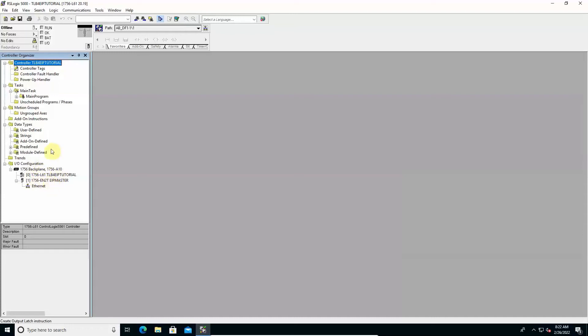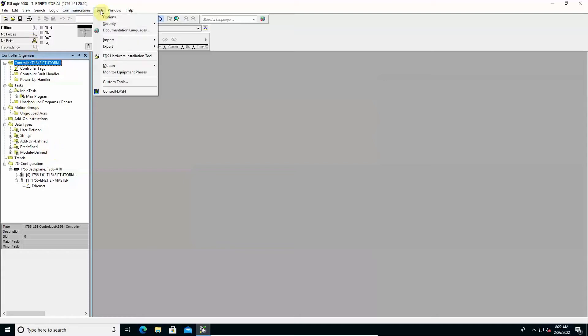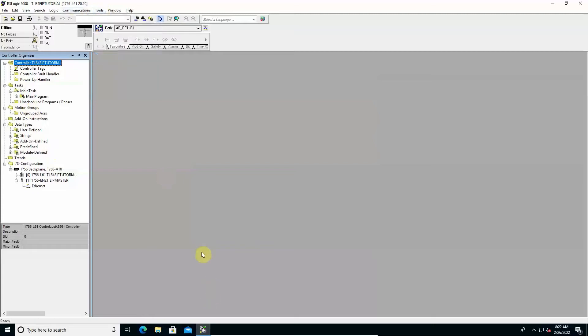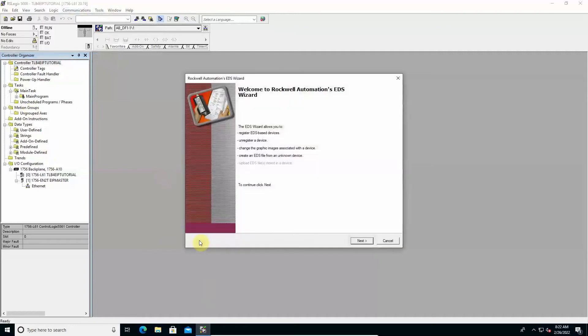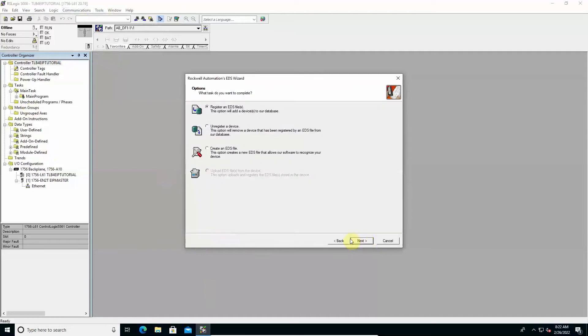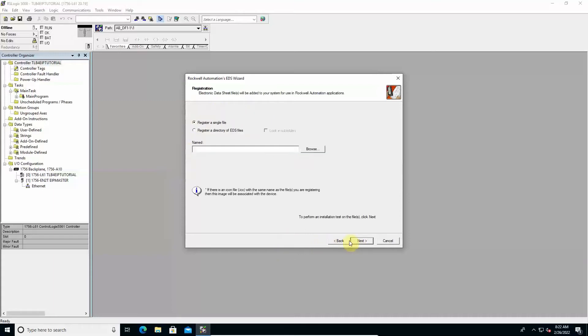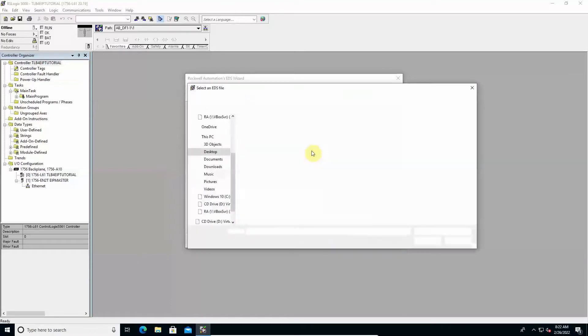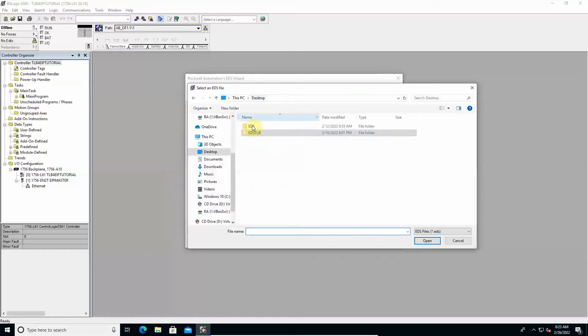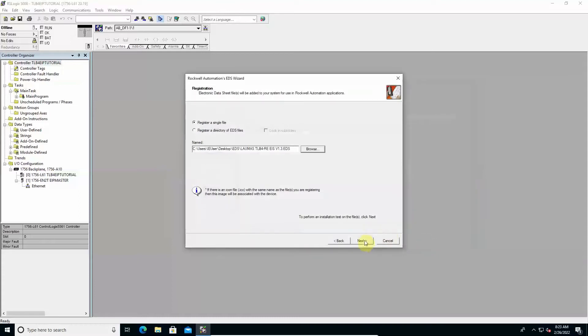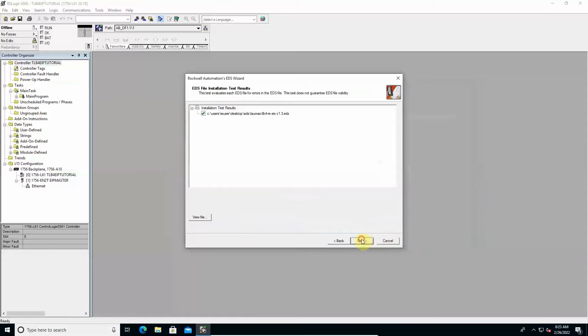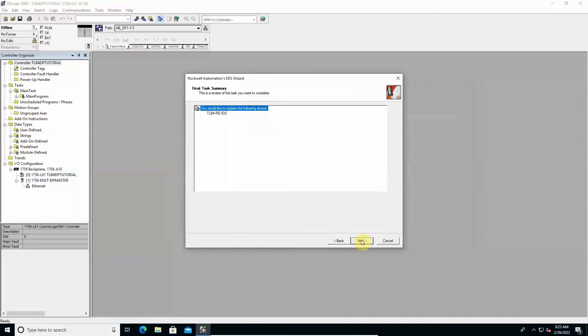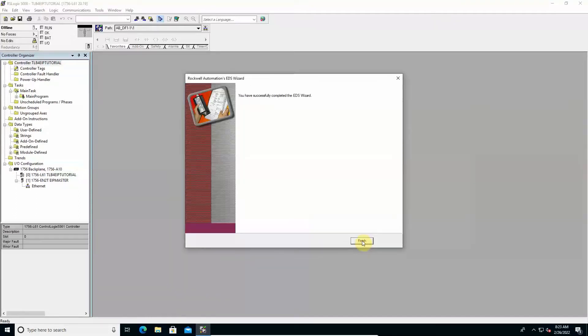The required operation to include the TLB4 instrument into the network is to import the TLB4 EDS file into the RSLogix 5000 catalog. Access the Tools menu and select the EDS Hardware Installation Tool item. A specific wizard starts. Click Next and select Register an EDS file. Click Browse and select the TLB4 EDS file. Click Next until the procedure is completed successfully.